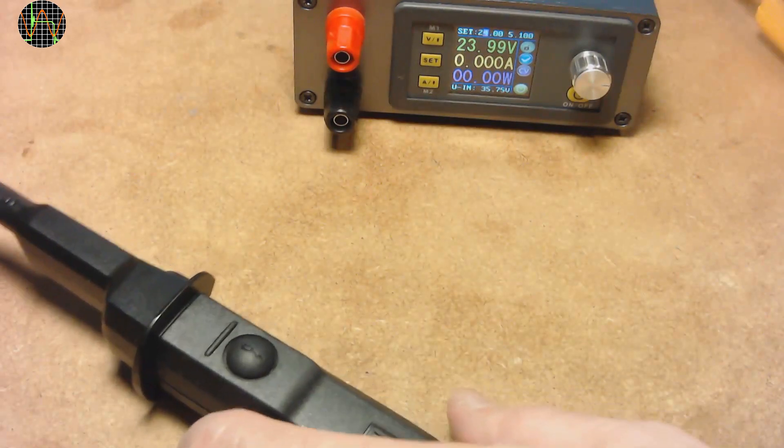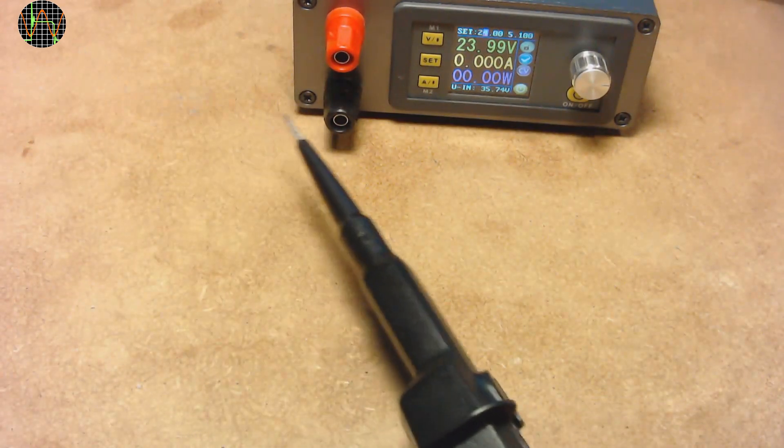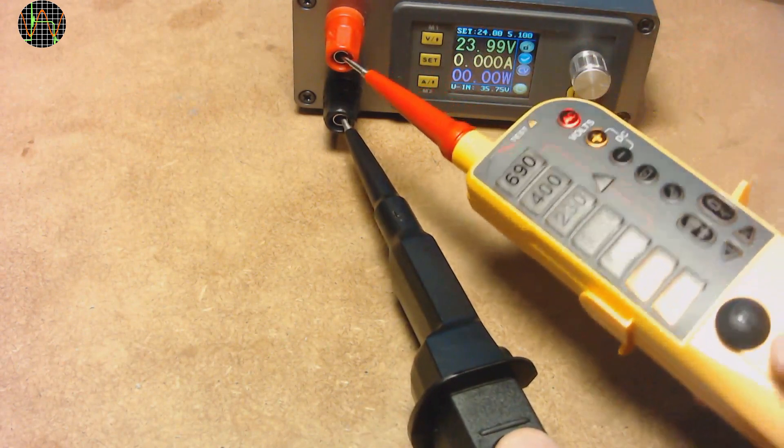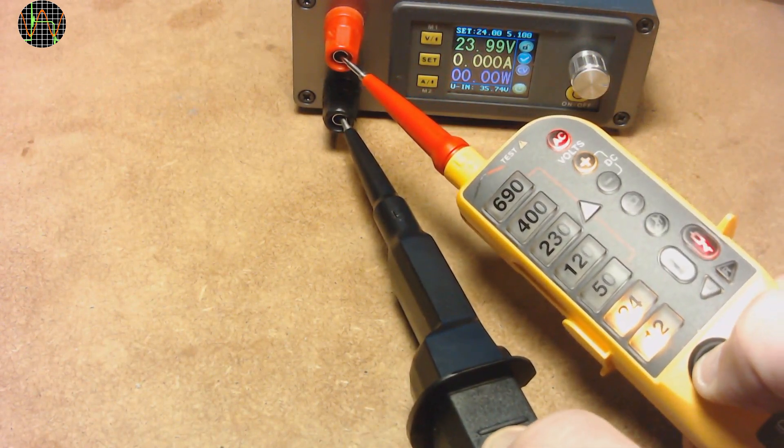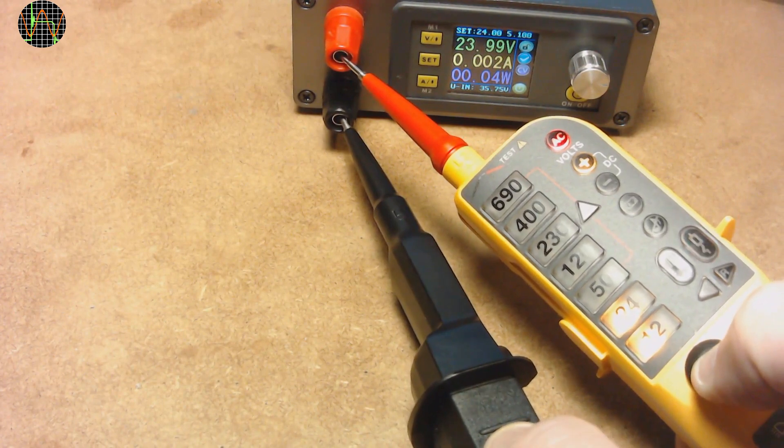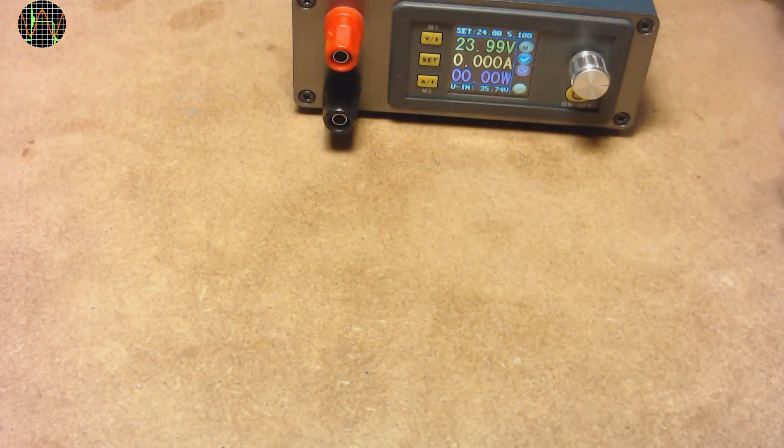Although the mentioned load test for tripping RCDs is of course meant for AC mains, you can see how it works when I use it here on the 24 volts DC. The current goes from 0 to 2 milliamps when the test buttons are pressed and the indicator lights up. The current would be of course much larger at mains voltage.